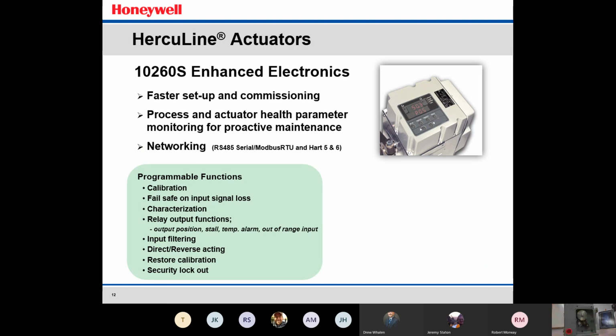You can do a characterization. So let's say, for example, you had a fuel-air ratio system and you wanted to do the curve of the fuel or air in the actuator. You could set up a linear characterization curve and then have the 4 to 20 milliamp hooked up to the actuator, and then based on that curve, the actuator would follow whatever you're putting into the actuator there.